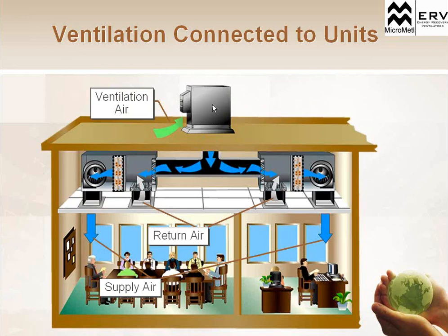So we can actually bring that pre-treated ventilation air into the HVAC system and then size it to do the rest of the job. Obviously, this HVAC system isn't going to be seeing that 95-degree outside air. It's going to be seeing 80 degrees, so we don't have to fully size it for outside air. We're going to reduce the size of the HVAC system that we talked about before, but it's still sized to temper that ventilation air along with that return air for set point requirements.